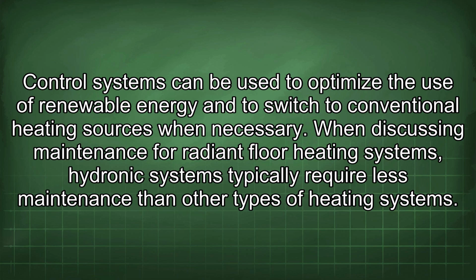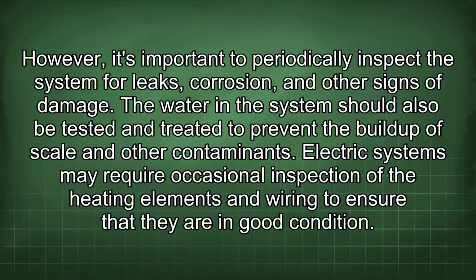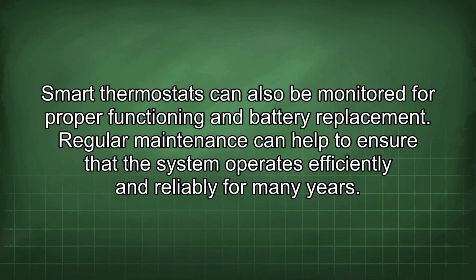necessary. When discussing maintenance for radiant floor heating systems, hydronic systems typically require less maintenance than other types of heating systems. However, it's important to periodically inspect the system for leaks, corrosion, and other signs of damage. The water in the system should also be tested and treated to prevent the buildup of scale and other contaminants. Electric systems may require occasional inspection of the heating elements and wiring to ensure that they are in good condition. Smart thermostats can also be monitored for proper functioning and battery replacement. Regular maintenance can help to ensure that the system operates efficiently and reliably for many years.